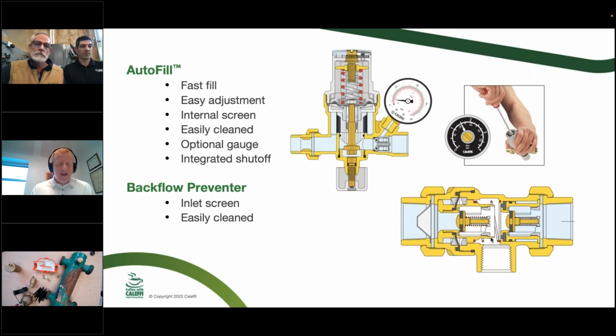And really, the fact is that if it's dripping on the ground through that vent between the two check valves, it's actually because it's doing its job, which is the silly part. And people get upset and they put in a new one. The new one does the same thing. Well, maybe it's an issue with the fact that you've got a lot of dirt and debris coming through there. And if it can't seal around those checks, it's going to drip.